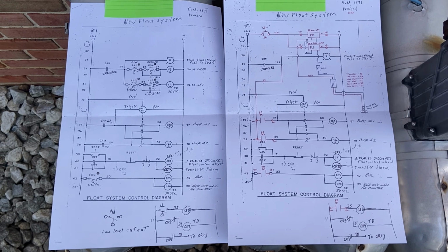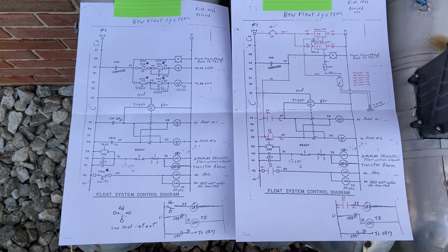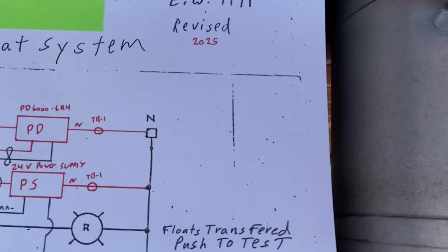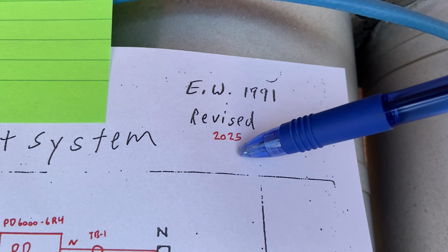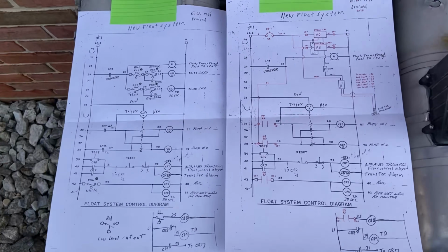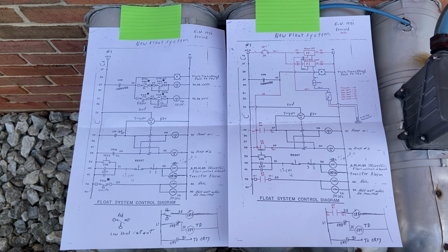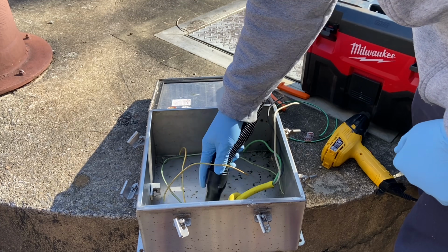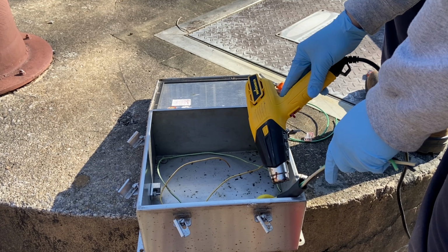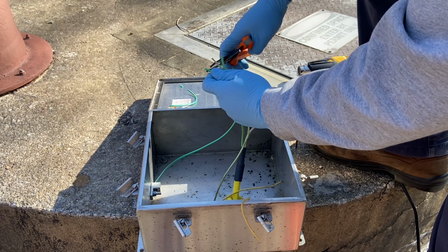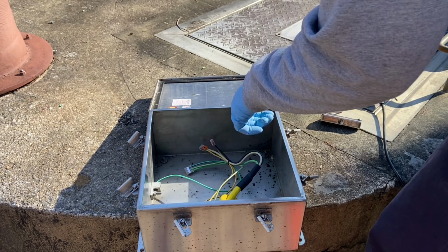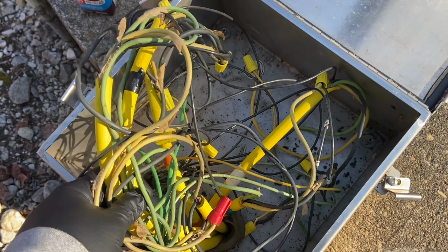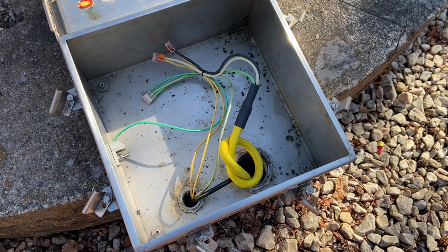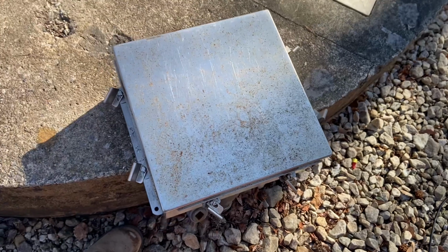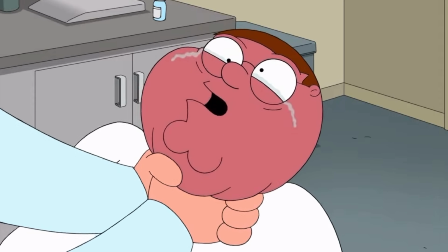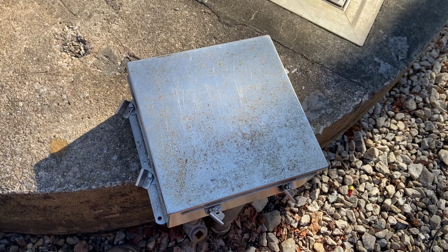So there you go. There's the old and the new diagram. Obviously I could have rewritten all of this in CAD, but that would have taken a lot of time. And look at that, revised 1991 and then 2025. Good God, these places need upgrades. So now we'll just tidy up the old float junction box, which is still a float junction box. It just only has 1 float instead of 7. And it's just that high well, which is only 24 volts. There's the old box, there's the new. Good God, that's beautiful. It's beautiful. That's the outside completely done.